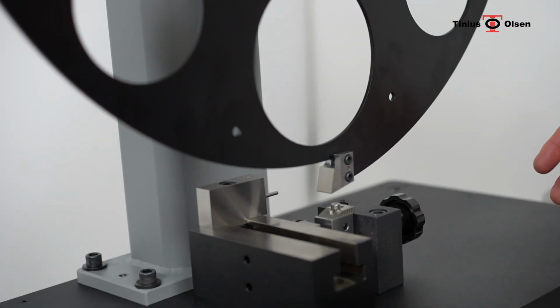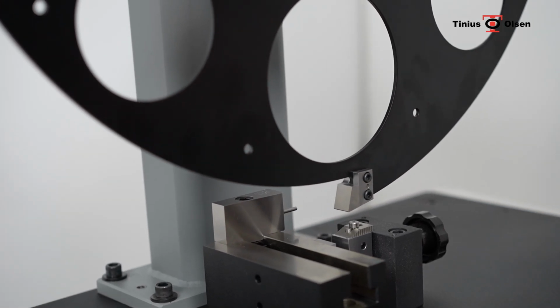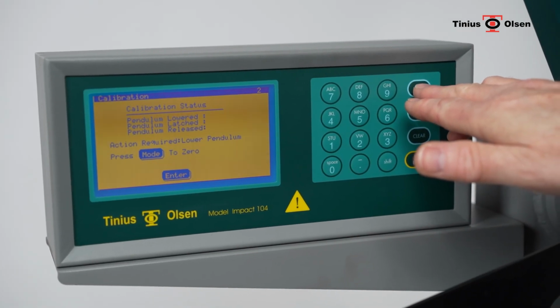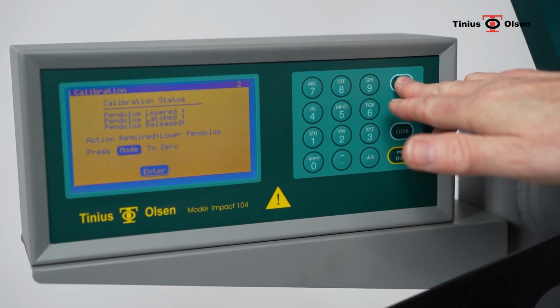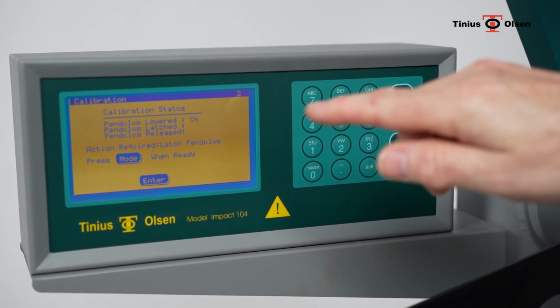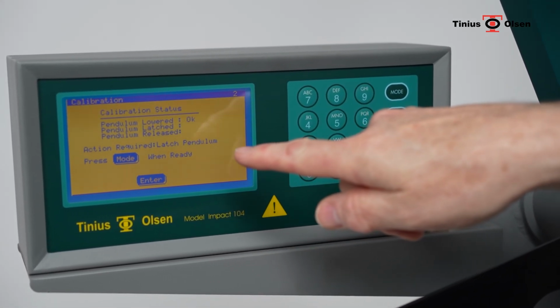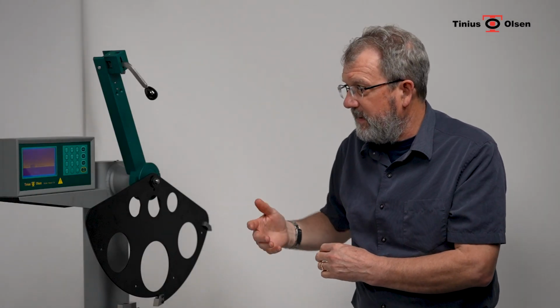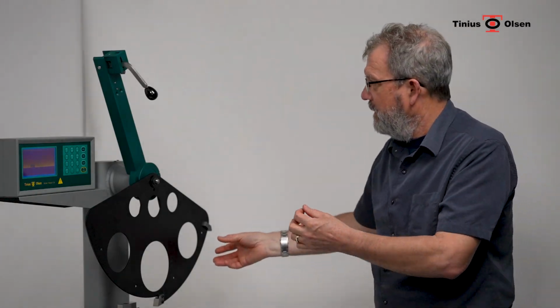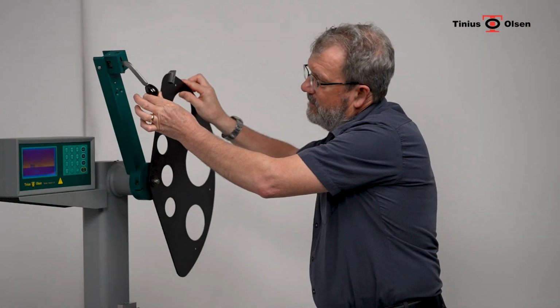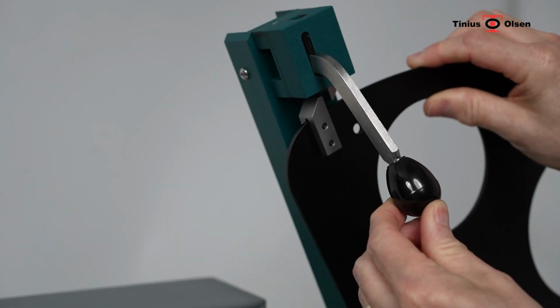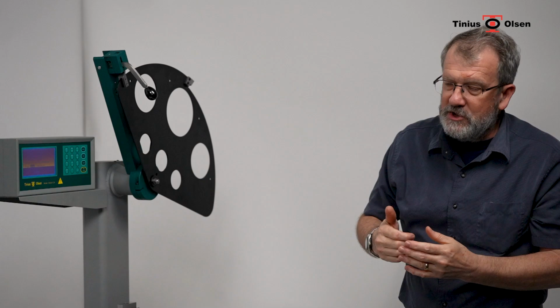So our pendulum is lowered, it is hanging freely, and we will press the mode button to zero. Pressing mode captures the zero position of the pendulum and stores it in the display. The next action required is latch pendulum, press mode when ready. So we simply take our pendulum, raise it, and latch it into the latched position.